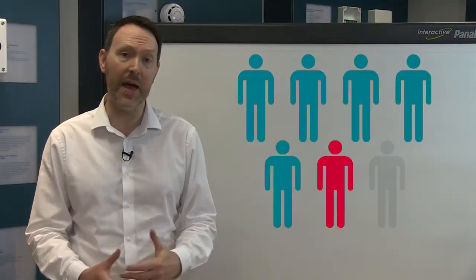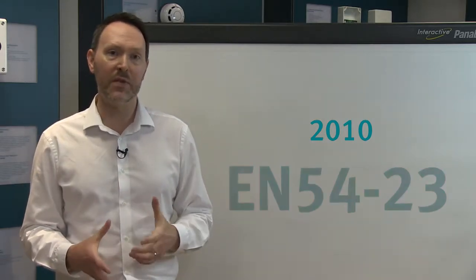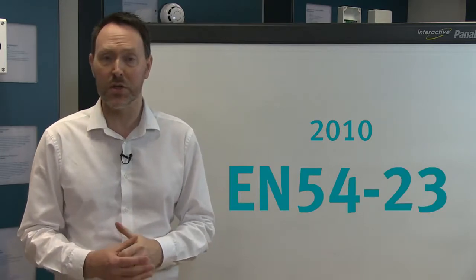1 in 7 people in the UK are deaf or hard of hearing, and they, as well as those who work in noisy environments such as factories, require a visual signal as well as an audio warning in the event of an alarm. Prior to 2010 there was no industry standard to determine the light output that a VAD should emit. Therefore, EN54 Part 23 was introduced to standardise the light output requirement.